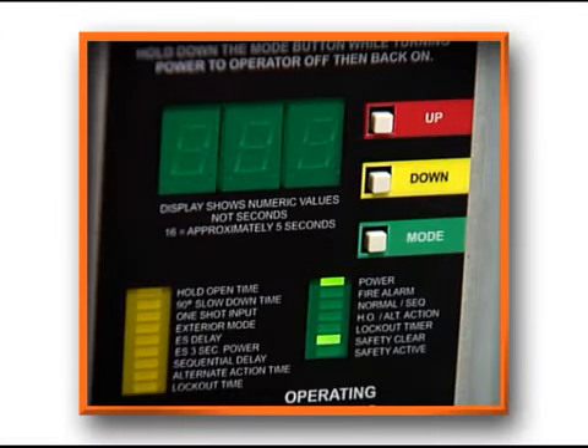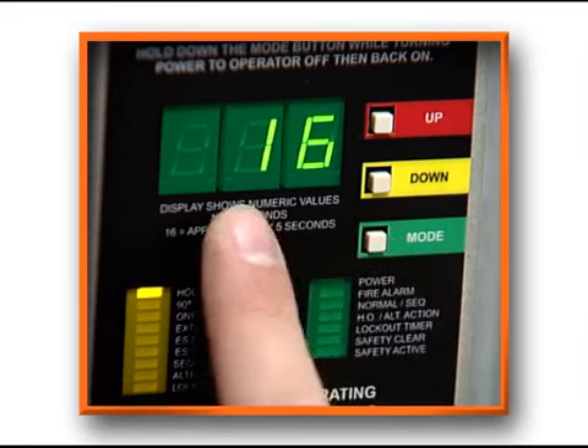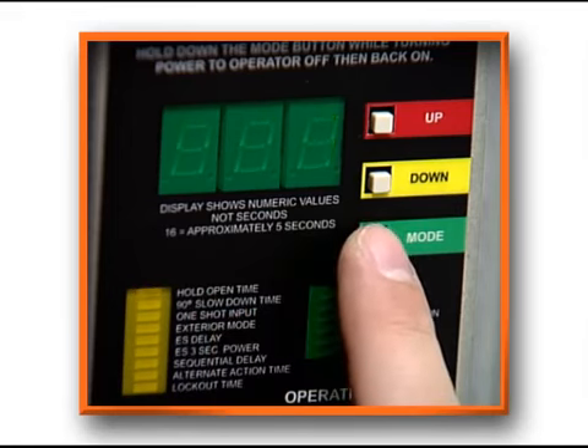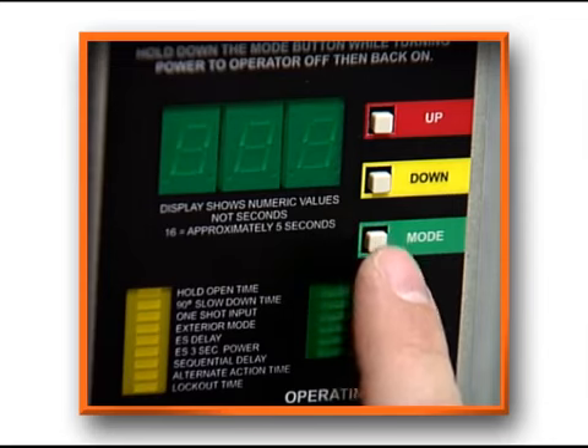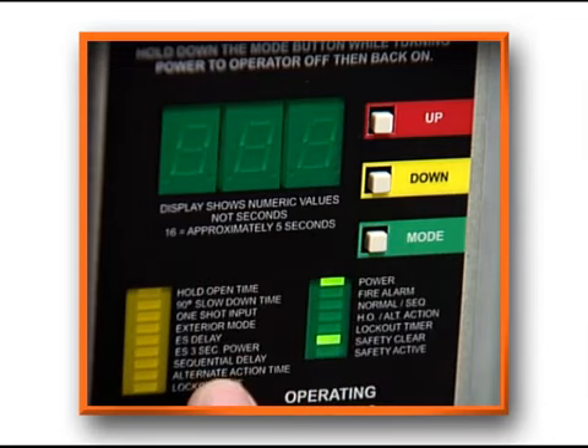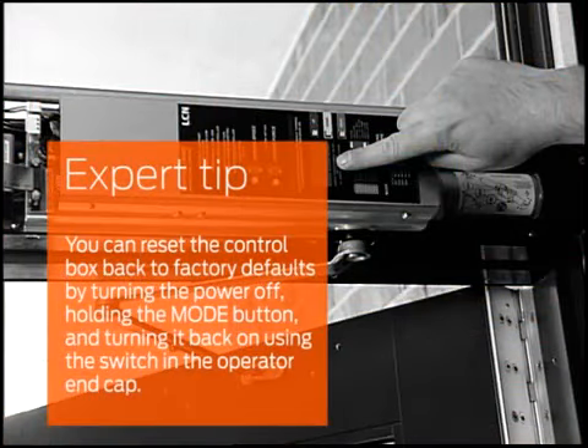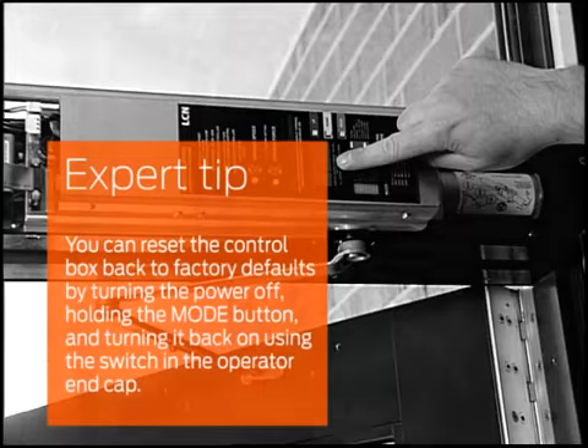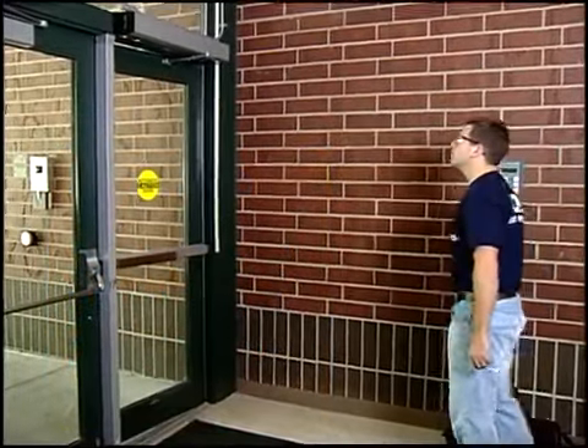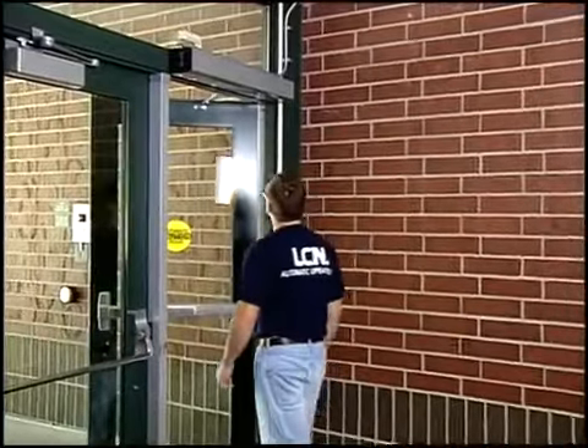The control box will automatically exit programming mode after 15 seconds with no input from the mode, up, or down buttons. The box also exits programming mode automatically when you've stepped through all programming options. You can reset the control box back to factory defaults by turning the power off, holding the mode button, and turning it back on using the switch on the operator end cap. In the next section, we'll wrap up the installation.